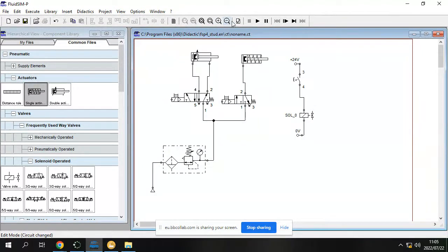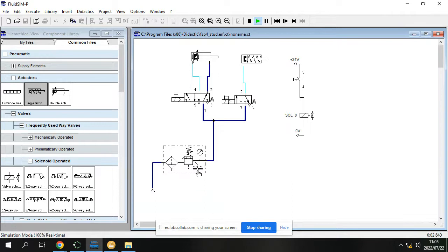So look what happens on the 5-2-way valve. Remember I said a double acting cylinder, you need to put tension on it so that you are guaranteed that it is at its end retracted position. So they do it by a valve. The valve is releasing air on one side so that the cylinder can sit in position and doesn't move. Because if the cylinder is loose, it can just extend. Let's say it's a vibrating system, and the cylinder is not fully retracted, or we don't have a compression that keeps it at the end retracted position, it will end up extending.